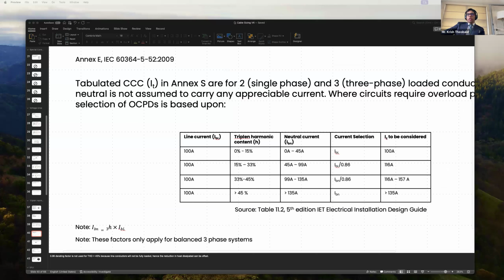Whether or not the armor can be considered as a protective conductor depends on whether it is terminated properly. But we are required to terminate it properly. If it is terminated properly, there will be fault current flowing in the armor, so you cannot neglect that. You still need to calculate the fault current in the armor, and ensure that the armor can actually withstand that amount of fault current for the time it is subject to it. So, whether a country accepts it or not, I cannot comment on.